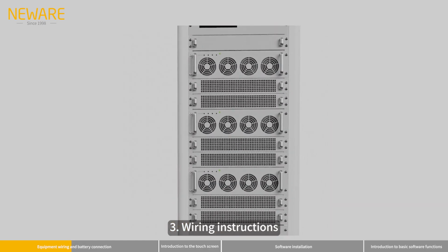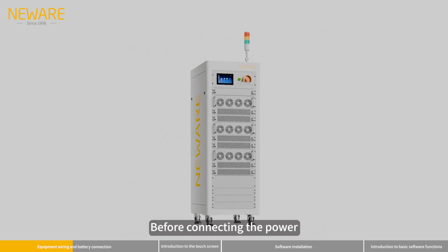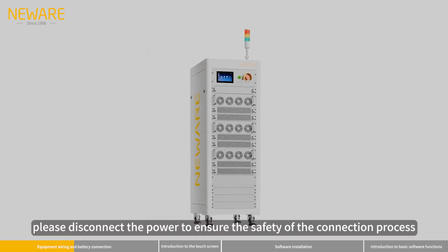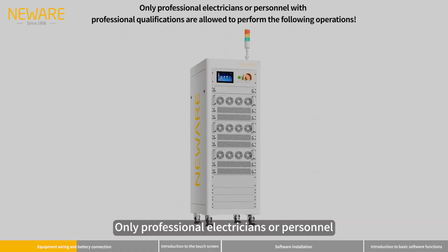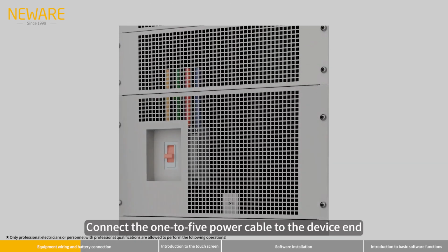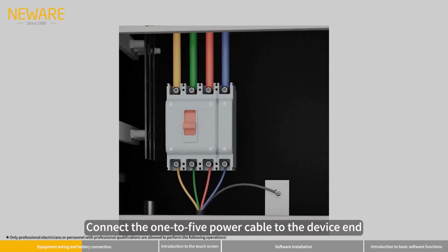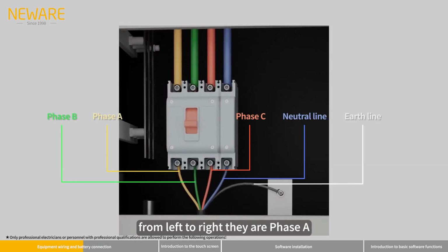3. Wiring instructions. Before connecting the power, please disconnect the power to ensure the safety of the connection process. Only professional electricians or personnel with professional qualifications are allowed to perform the following operations. Connect the 1 to 5 power cable to the device end. From left to right they are Phase A, Phase B, Phase C, neutral line, and the protective earth line, also known as the ground line or PE line.